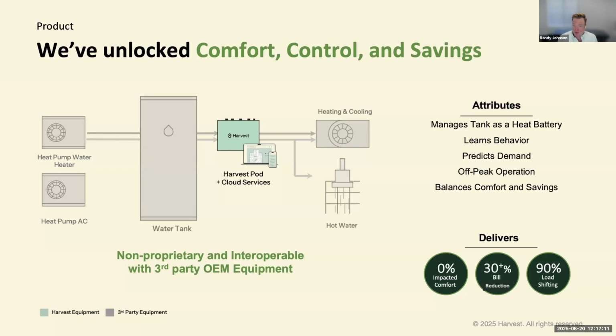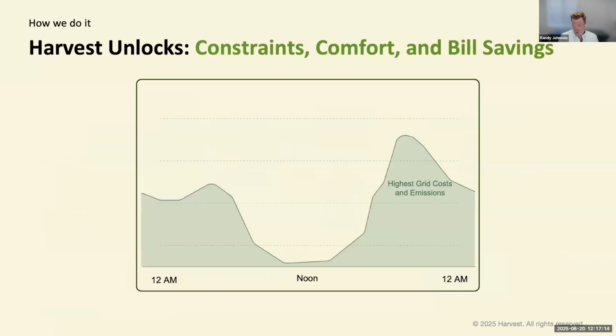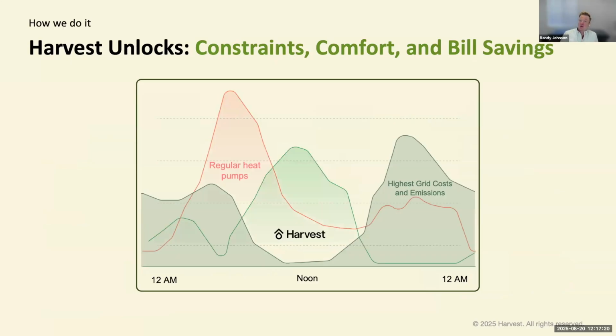Ultimately, what that delivers for us compared to traditional heat pumps from an operating perspective is we're able to shift the gross majority of the electrical consumption and heat pump operation to the middle of the day when renewables are abundant. The ambient air temperature is higher, which improves the coefficient of performance of the heat pumps. And because we're scheduling when they run, it's not an on-off call like you'd normally get from a thermostat - we're running the heat pump for an extended period of time, which reduces stress on the condensers and potentially increases the lifespan of the equipment within the system.